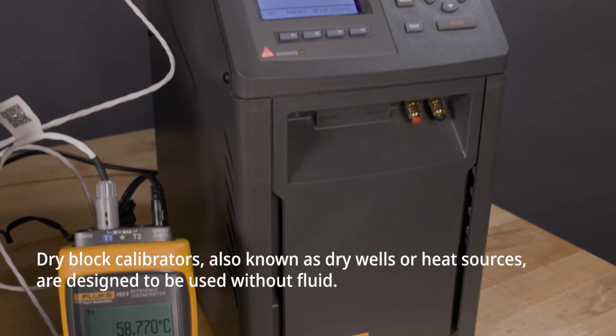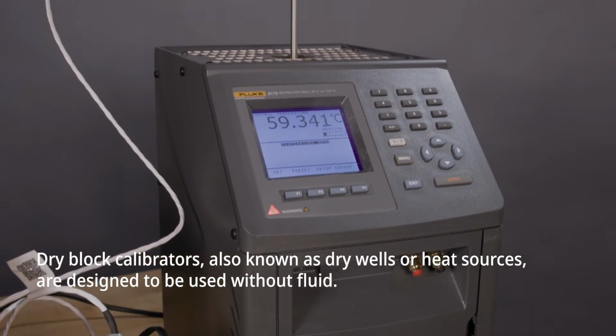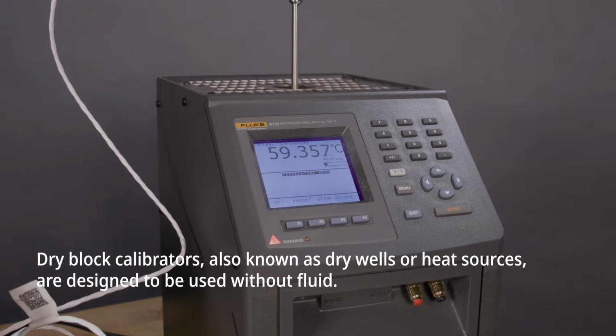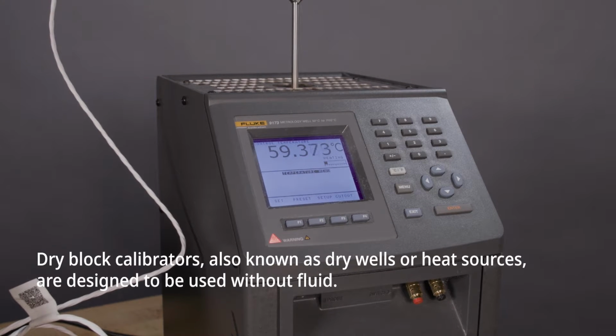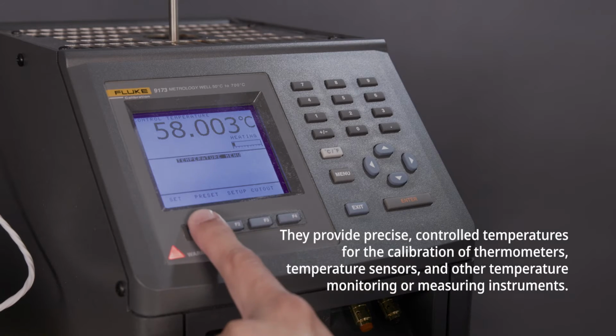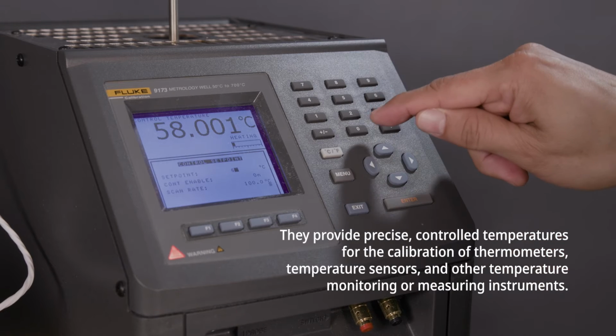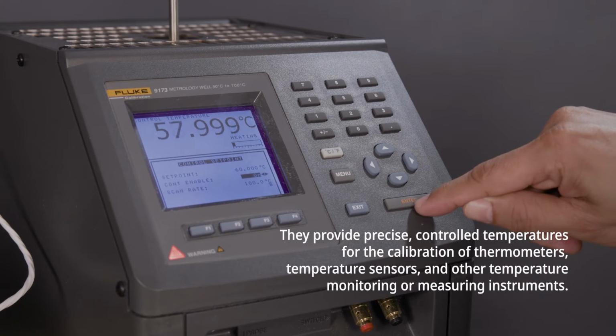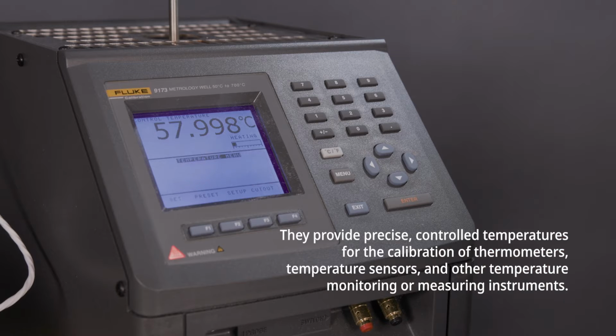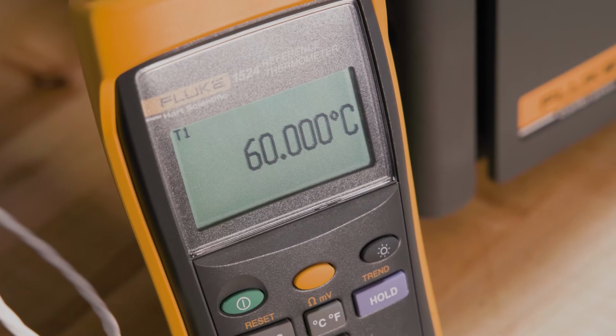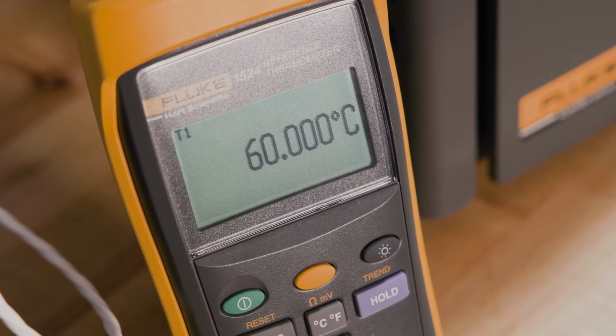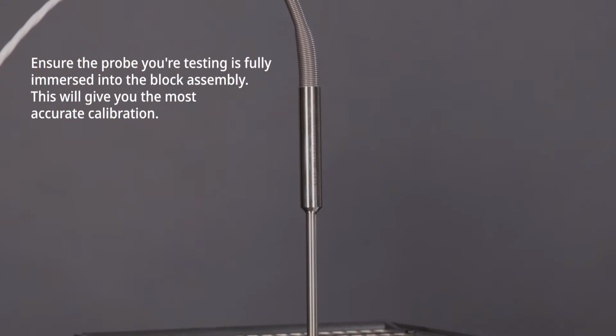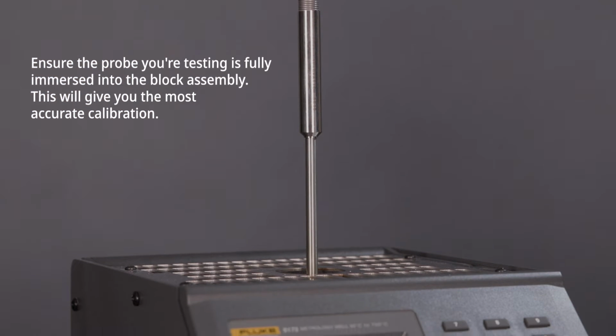Dry block calibrators, also known as dry wells or heat sources, are designed to be used without fluid. They provide precise, controlled temperatures for the calibration of thermometers, temperature sensors, and other temperature monitoring or measuring instruments. To calibrate an RTD, firstly ensure the probe you're testing is fully immersed into the block assembly.